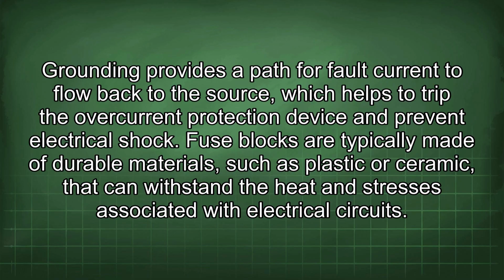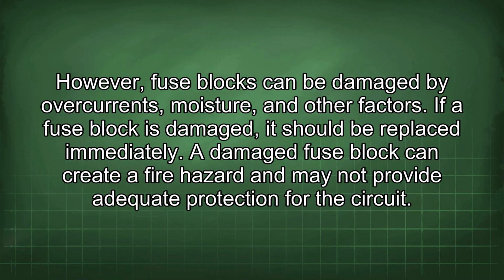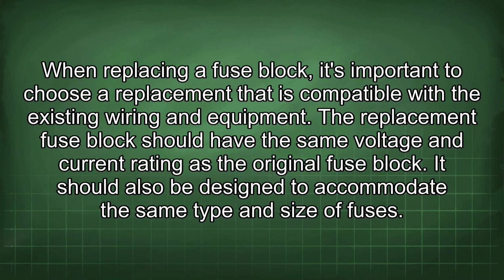Fuse blocks are typically made of durable materials, such as plastic or ceramic, that can withstand the heat and stresses associated with electrical circuits. However, fuse blocks can be damaged by overcurrents, moisture, and other factors. If a fuse block is damaged, it should be replaced immediately. A damaged fuse block can create a fire hazard and may not provide adequate protection for the circuit. When replacing a fuse block, it's important to choose a replacement that is compatible with the existing wiring and equipment. The replacement fuse block should have the same voltage and current rating as the original fuse block. It should also be designed to accommodate the same type and size of fuses.